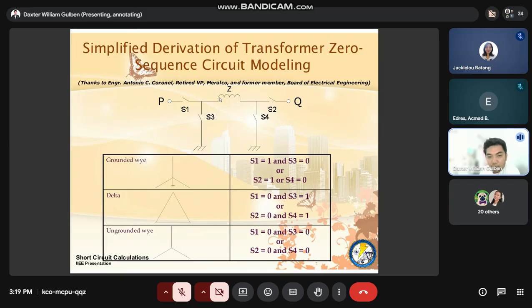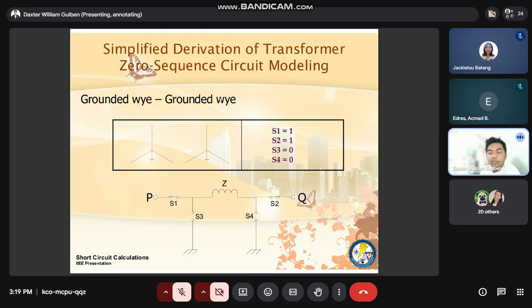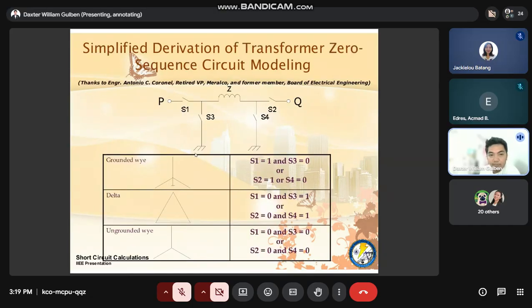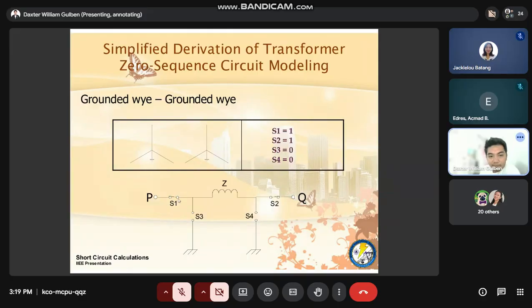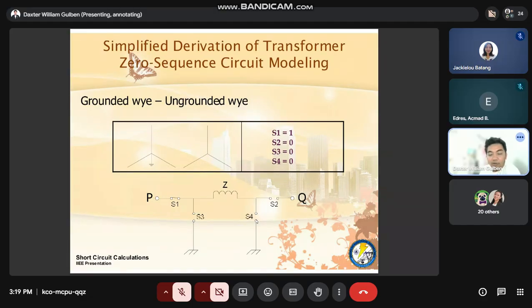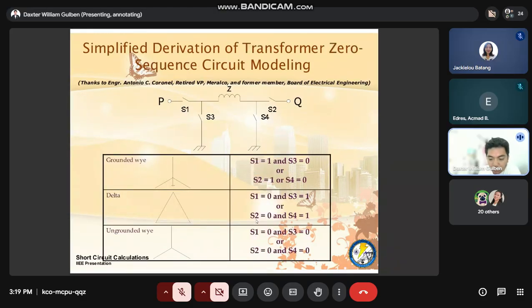So how do we apply this one? If you take a look here, for a transformer you have a primary and a secondary. So it's possible for the primary to have a different configuration from the secondary. In this case, if it is grounded Y, what is the ruling? Based on this connection, if grounded Y, close here, open here. For a grounded Y secondary, close here, open here. Okay? Understood? Now if it is ungrounded Y, based on the ungrounded Y, all of the switches are open.